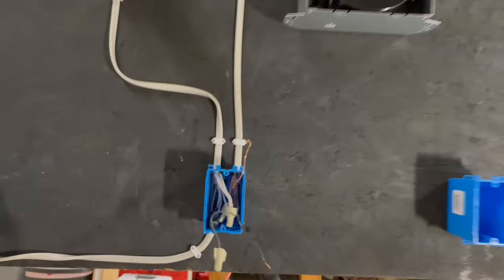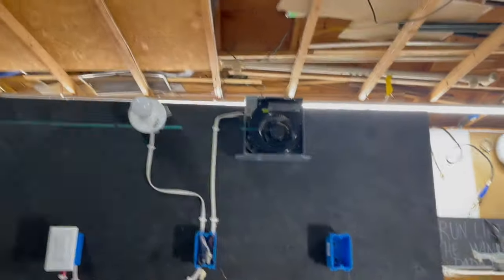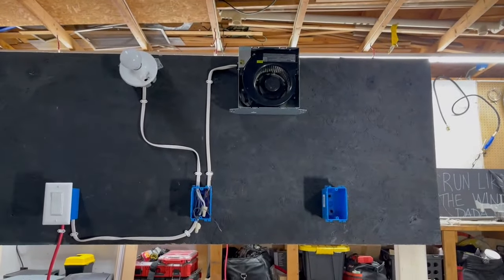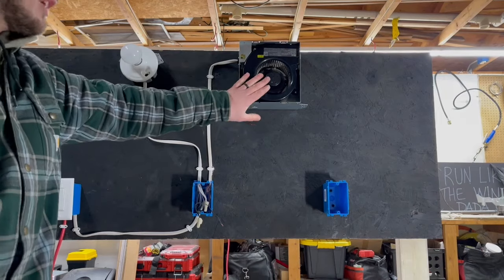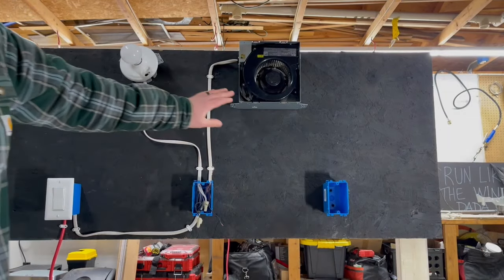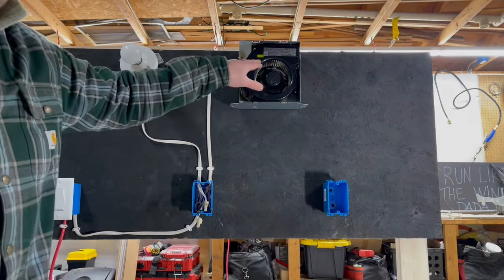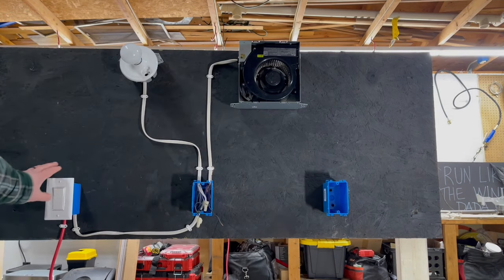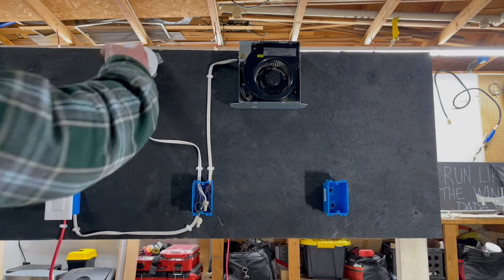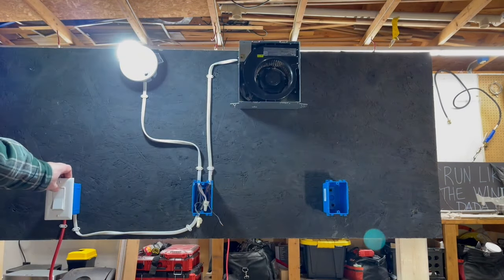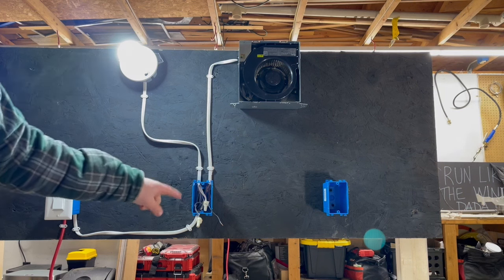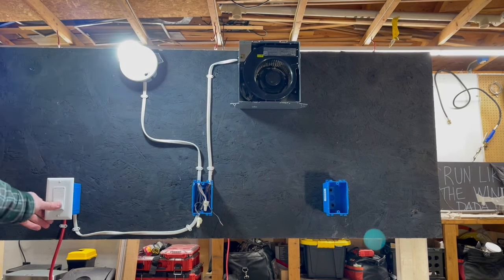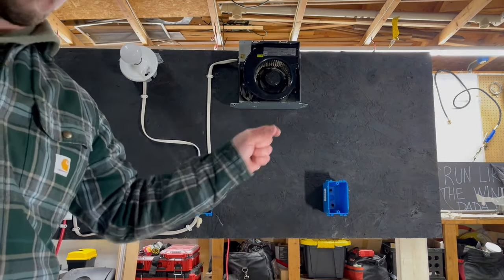Let's back this camera up. Now I purposely have the cover off of our exhaust fan here so that you can see it when the light turns on and the fan runs because it's a quiet exhaust fan so you're not going to hear it. So let's turn our breaker on and see if the light or the fan turns on. Okay, so we know that that switch leg will be our light. So let's make that the top of our switch.